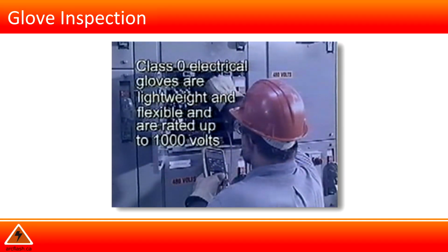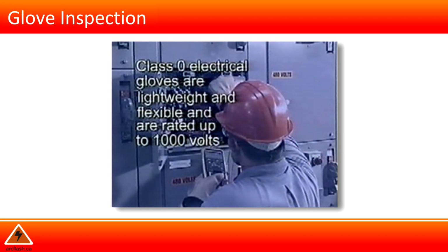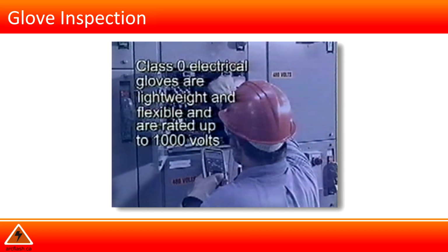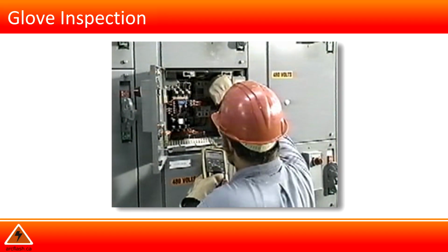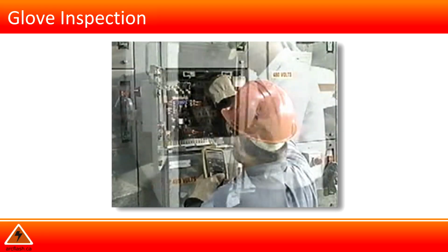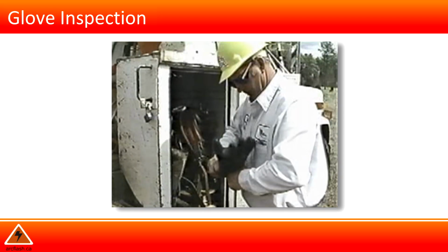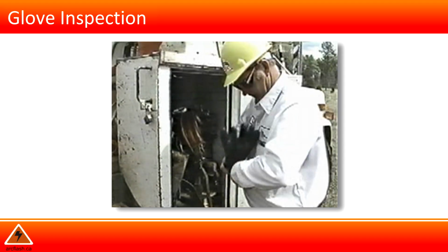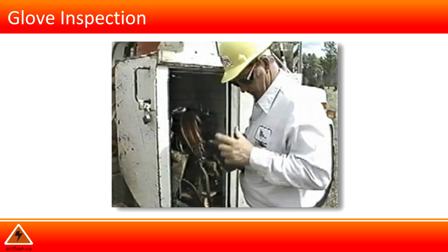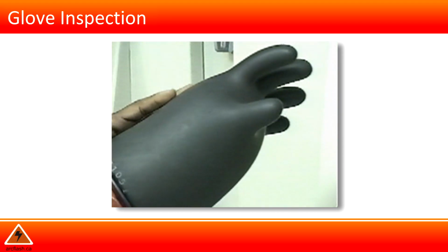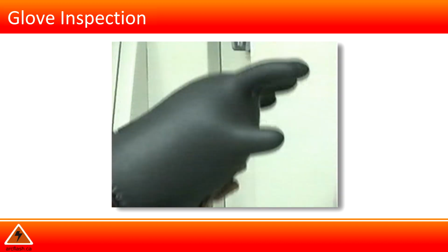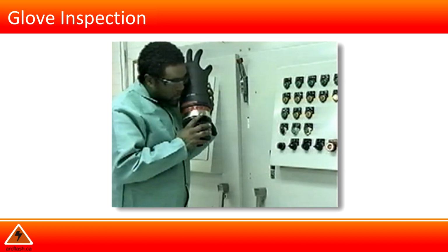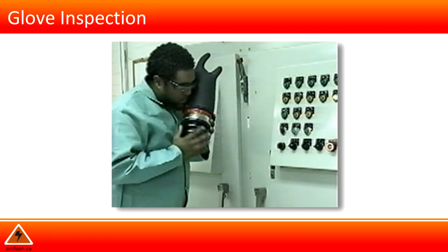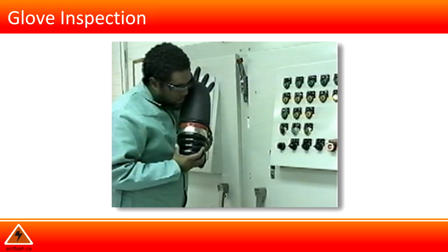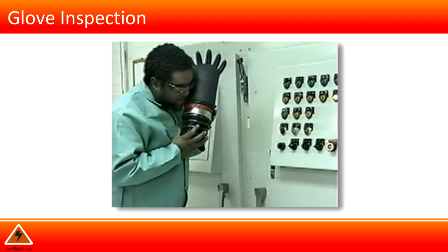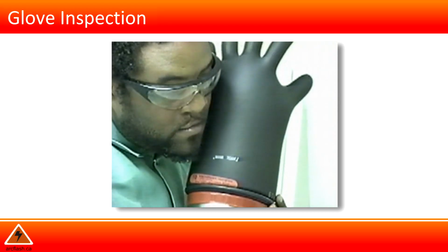Class 0 electrical gloves are lightweight and flexible and are rated up to 1,000 volts, making them a good choice for many applications. No matter what class glove or voltage level you are working with, always inspect your gloves before each use by capturing air into the glove and inspecting the glove for holes and leaks. Because electrical current can find its way through even the smallest of holes, hold the glove near your cheek and feel for any air escaping from a hole which may be too small to see.